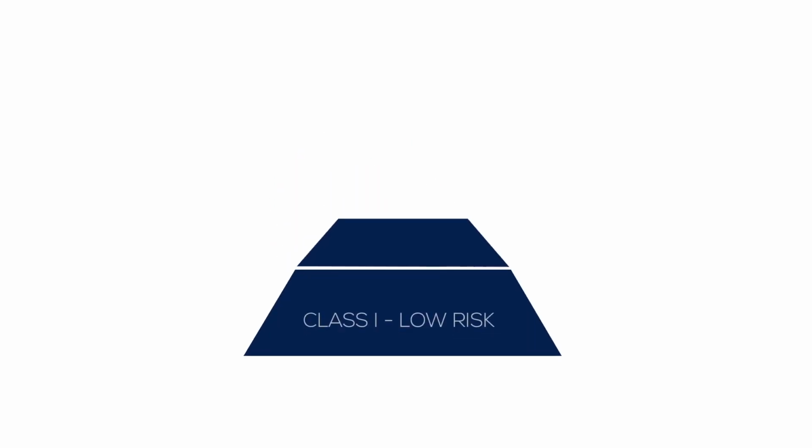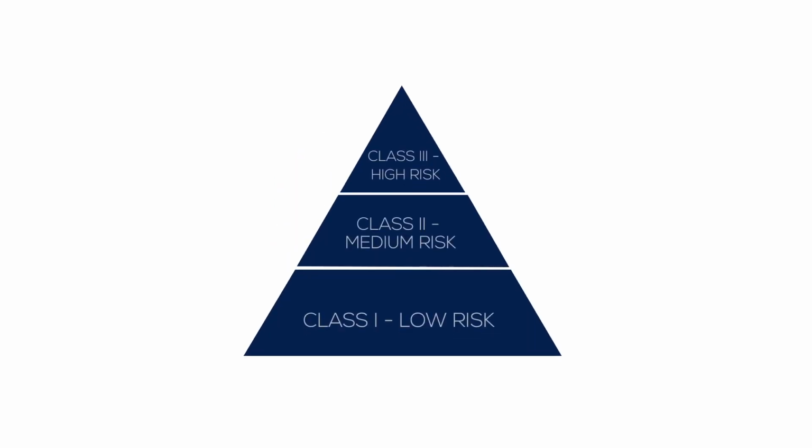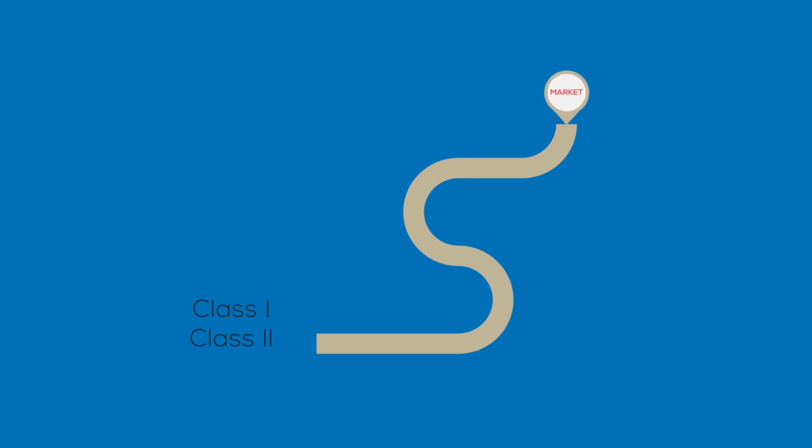The FDA classifies medical devices in 3 risk categories depending upon use and severity. Each product category has a unique code which can be used to classify your device based on existing products. For Class 1 and Class 2 devices, the usual route to market is so-called 510K pre-market clearance.